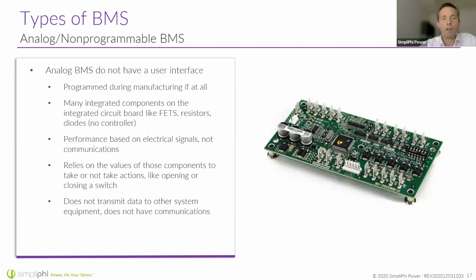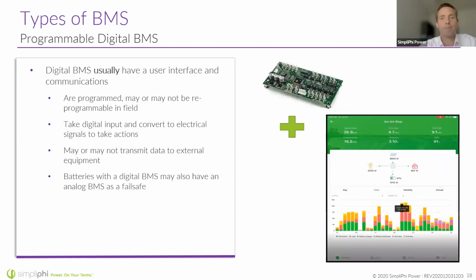The performance is based on electrical signals coming from the individual components of the battery, not from communication. So this is an analog unit, meaning it's not actively communicating with other equipment in an energy storage system. It relies on the values already set on these components to take action in terms of balancing and protecting the battery. This analog system does not transmit data, so there's no communication built into it—it's not transmitting information to other components of the battery or the ESS system.